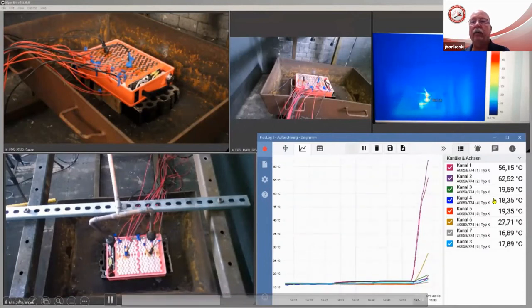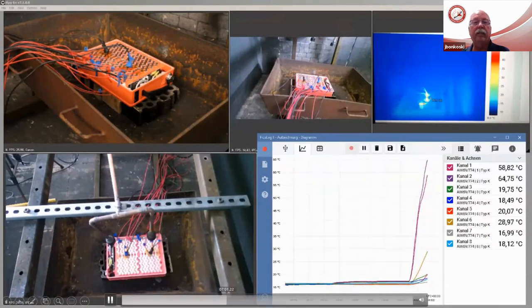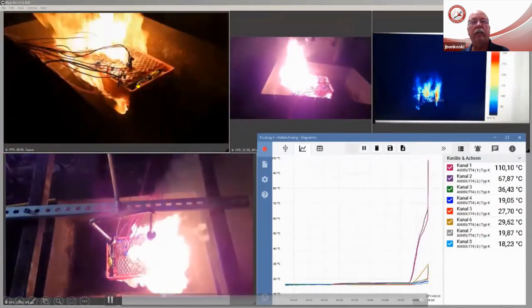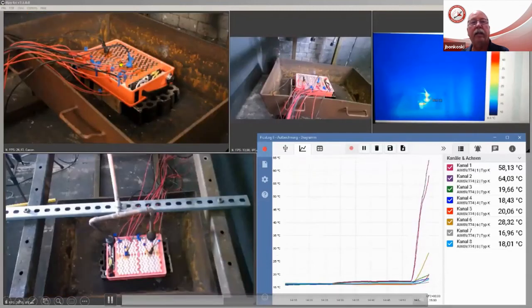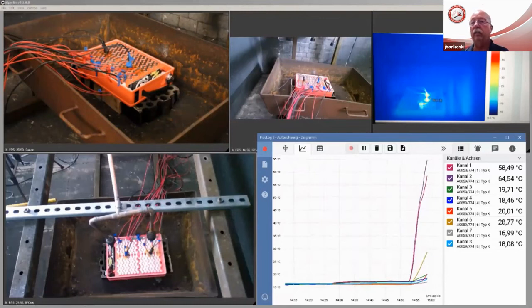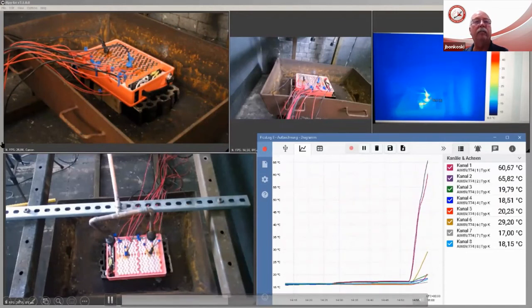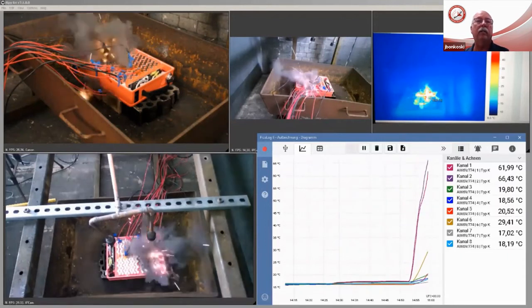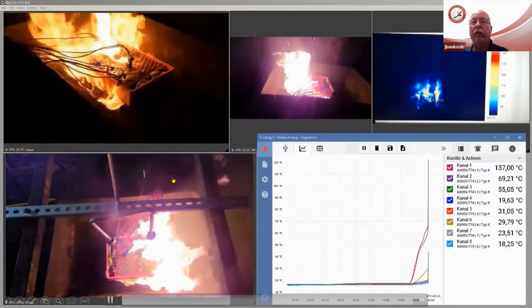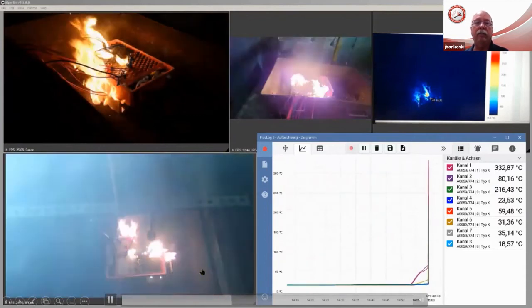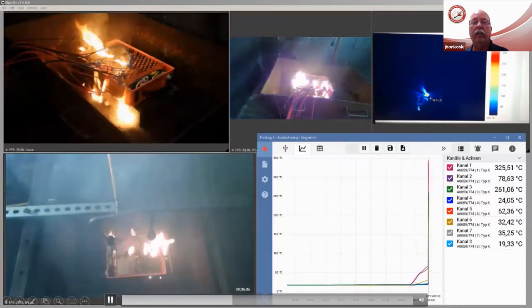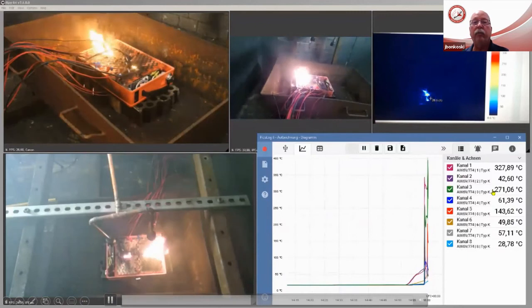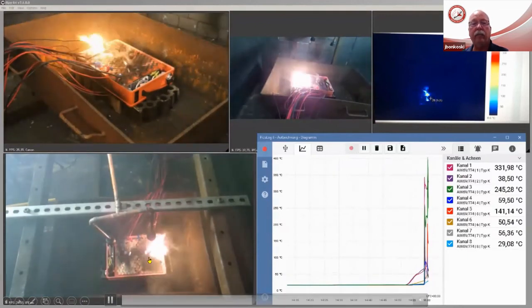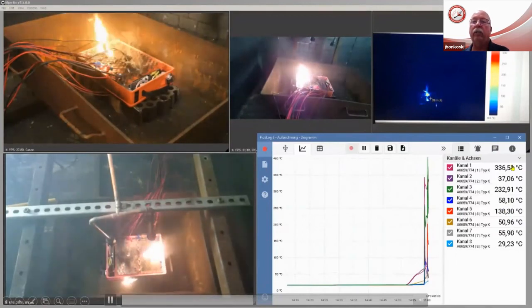We sit there and we can see our temperature starting to rise a little bit on our cells. Now we get into that thermal runaway - let me back it up a little so you can see that heavy smoke that starts to build. Once we start seeing that heavy smoke, like we've seen in the videos with the car being charged and all the other batteries we've seen, we see that little puff of smoke just before those batteries fail. So you're going to see the top left video there - it's going to start, and then all of a sudden we get into our one battery that may have failed. That one battery has enough energy and enough violent reaction in it where it causes enough heat to cause the battery next to it to go. As we go through and continue to see the fire grow, we'll watch our temperature sensors on the bottom here.